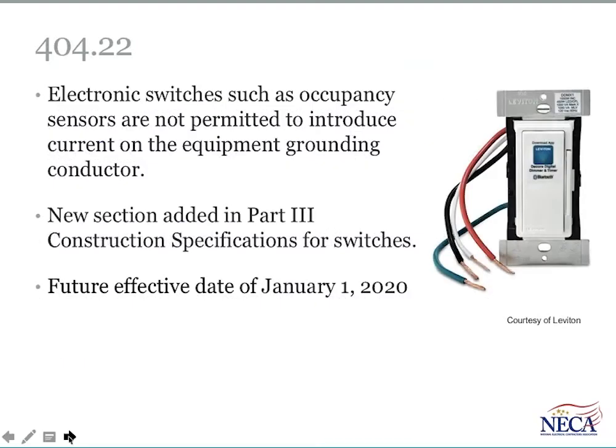A companion change to that one that requires the grounded conductor in the switch locations is a new section, 404.22, in Part 3 of Article 404. And Part 3 of the article deals with the construction specifications for switches. And there's new language that was inserted there to clarify that electronic switches, such as occupancy sensors and so forth, are not permitted to introduce any current on the equipment grounding conductor, which is basically going to cause a change in the product standard for developing those types of devices.